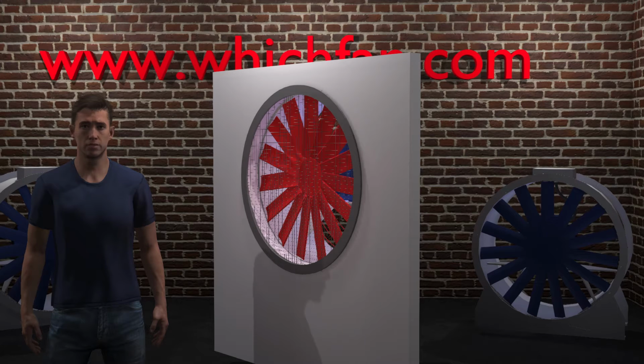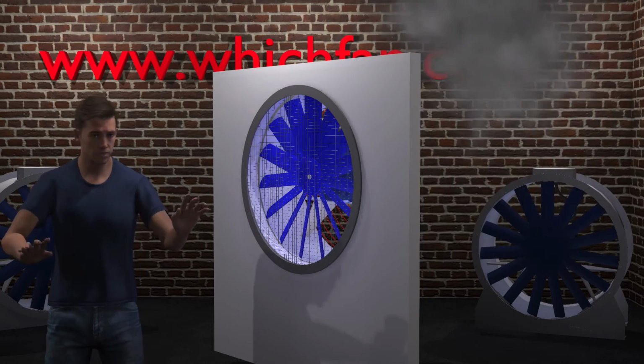Okay, so now let's look at Form B airflow. I'm pretty sure you will know what this is now. This is air through the impeller then over the motor, so opposite to Form A. If you were standing behind the motor of the fan, the air would be blowing at you.